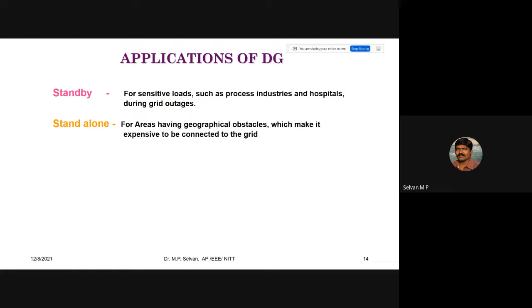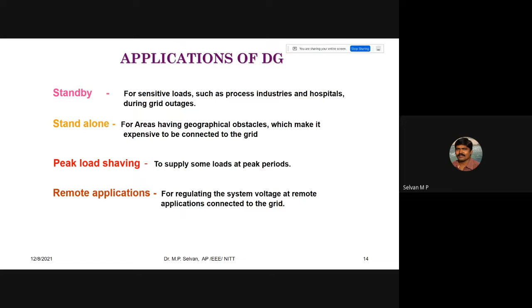These distributed generators have many applications: standby, standalone, peak load shaving, remote applications, and combined heat and power. You know all these things. The only point I want to stress here is that distributed generators are designed to work only with the grid. What I mean is, if the grid is not available, these generators will be disconnected. Are you getting the point? You can have a 2 megawatt solar power plant, connected to the grid and operating in parallel with the grid.